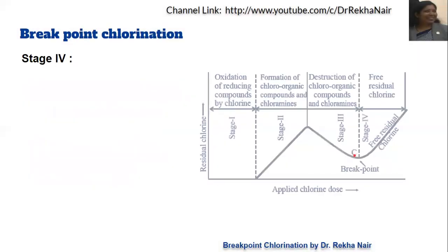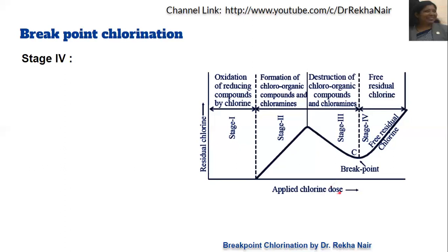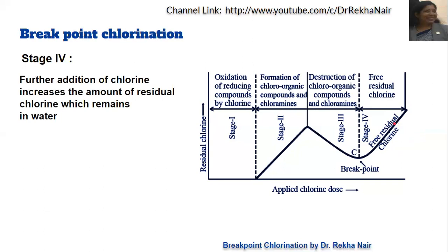In Stage 4, if we continue applying more chlorine dose, there is an increase in residual chlorine. This is because at the breakpoint, complete destruction of all organic compounds, ammonia, chloramines, bacteria, and germs has already occurred, giving almost 100% disinfection. Any additional chlorine added simply increases the chlorine level in the water — this is called free residual chlorine. So in Stage 4, we get free residual chlorine.